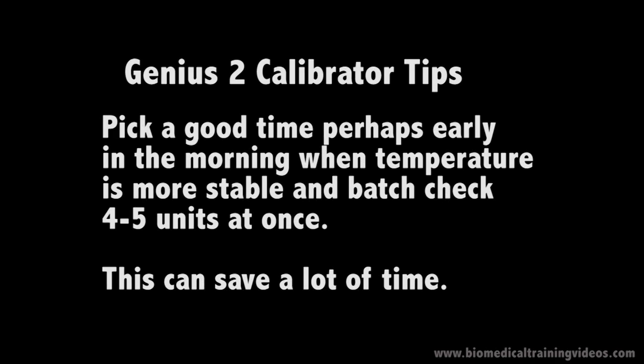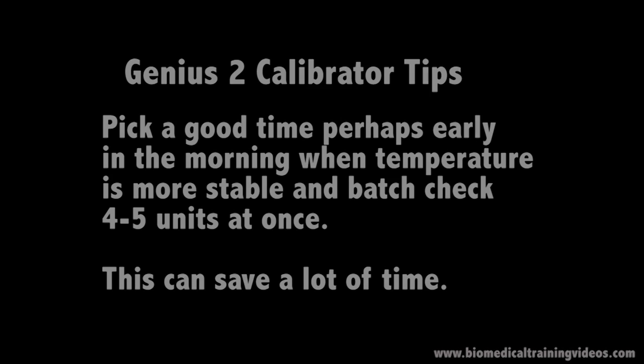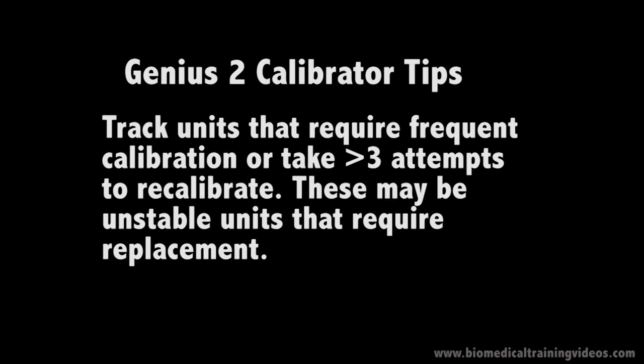And once you get the calibrator set up, it's a good idea to perhaps do all the units you've got in the workshop in one go if you can. This can save you a lot of time. And it's also worth tracking those units that require frequent calibration or take greater than 3 to 4 attempts to recalibrate. This might indicate they're unstable and may require replacement.